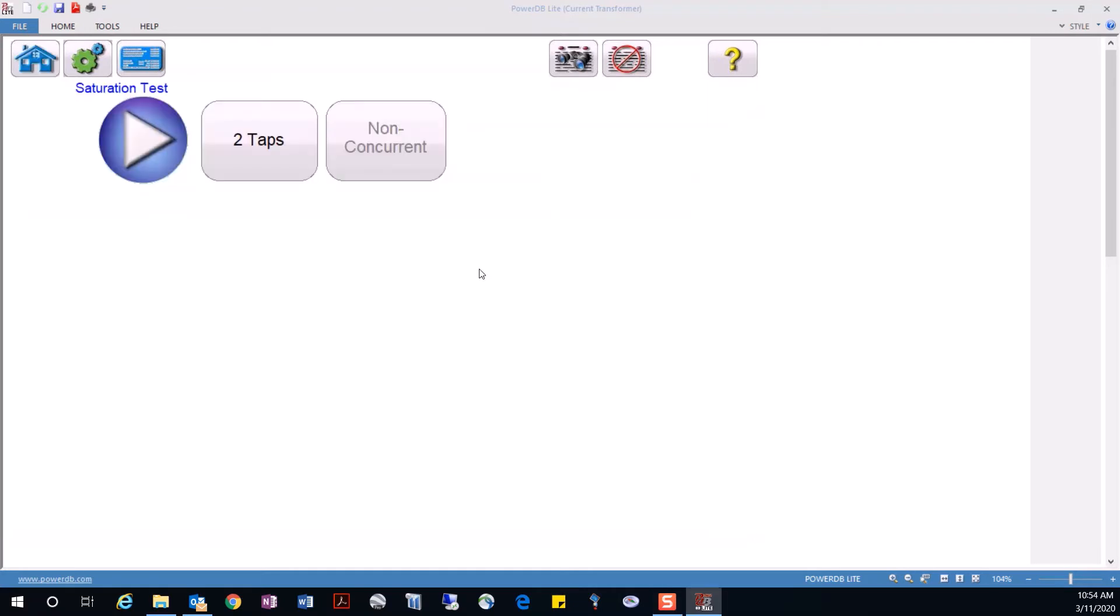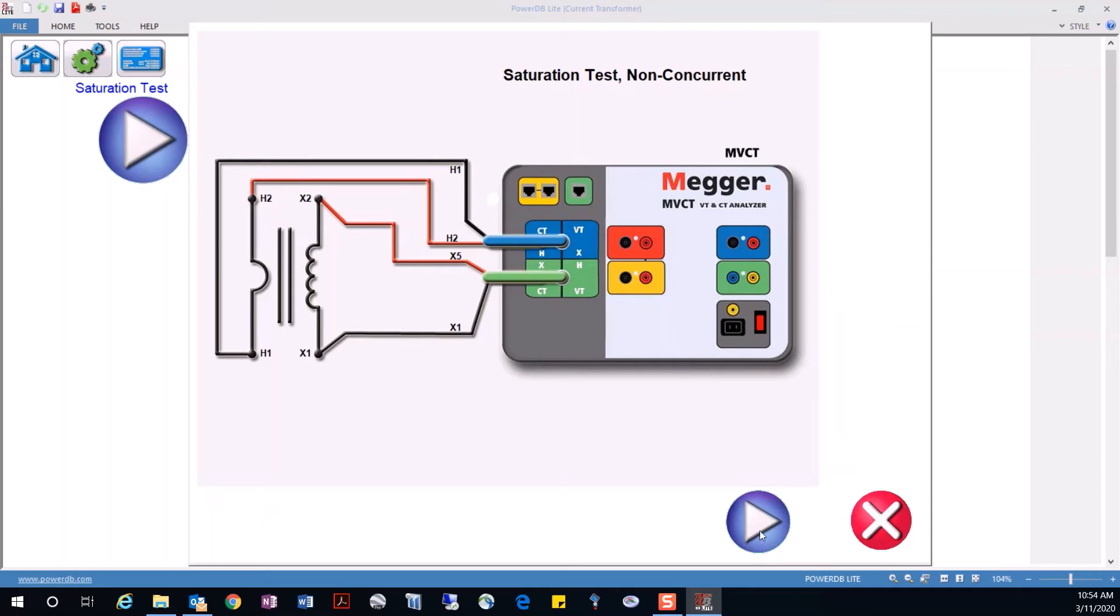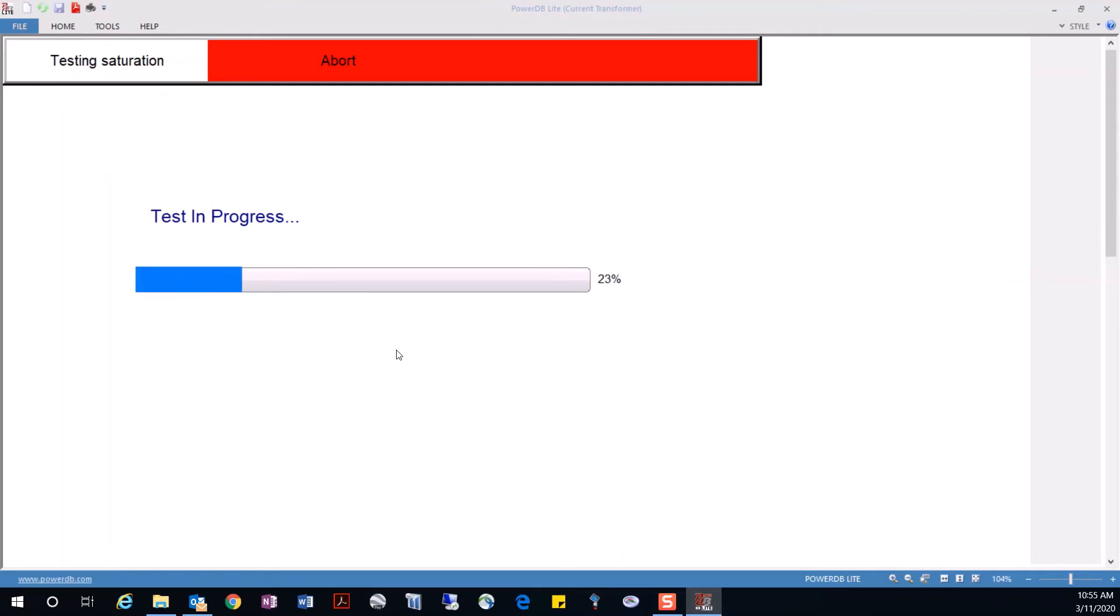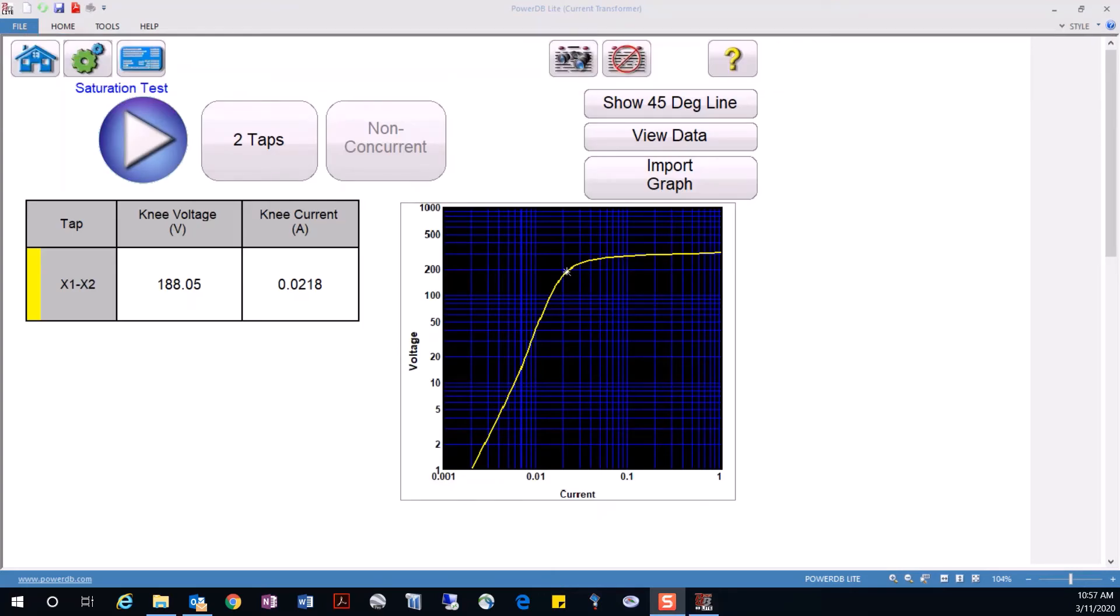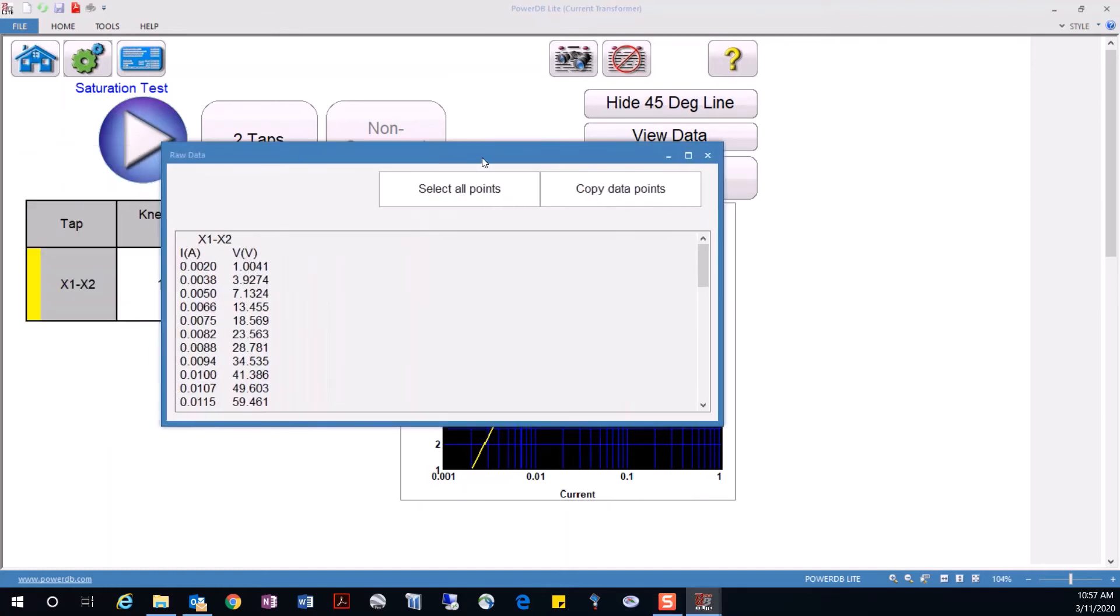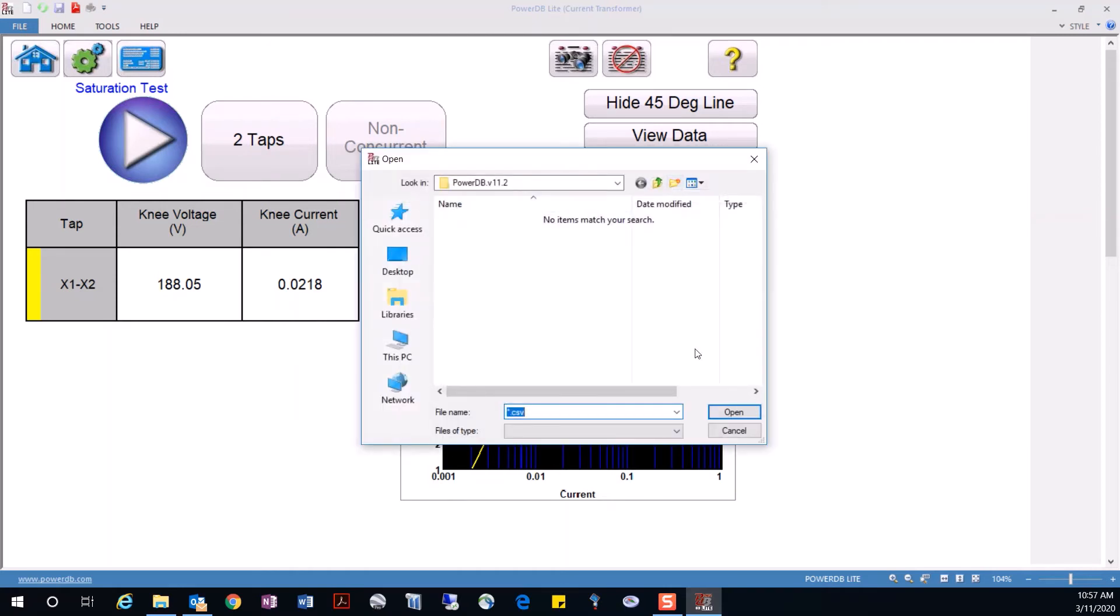The next testing run is for saturation characteristic. We confirm correct connections, hit the run button and testing starts. It is worth pointing out that all these interface screen recordings are fast forwarded in this presentation. The actual instrument takes longer to run the testing. We get the results displaying the saturation curve on the right and the coordinates of the knee point on the left. We have the option of displaying the knee point tangent line, we can view and copy the data points, and we also have the option of importing data points from a previous test for comparison. Finally, we add the results to the customer report.